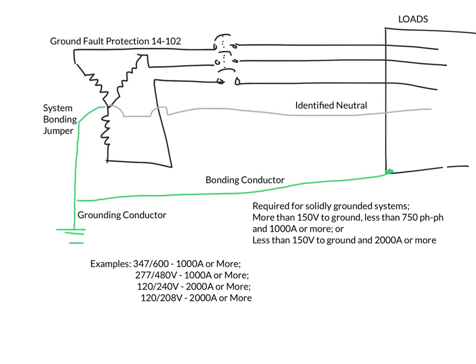So I'd mentioned that these types of faults don't necessarily open up the overcurrent device. The issue with these types of circuits is that when we develop a fault on these systems, the fault itself produces an arcing fault. Now, arcs themselves can act like resistors in the circuit. So if I've got a main breaker rated at, say, 1,200 amps, but that arcing fault is behaving like a resistor in the circuit, it can slow my fault current down well below the 1,000, 1,200 amp rating of that breaker and allow the fault to persist without the overcurrent device opening up.